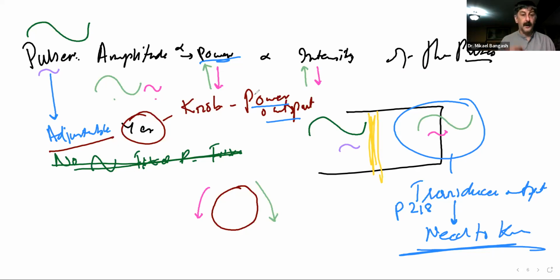Now, acoustic, I told you, acoustical is just a fancy word for sound. Pulser power: greater pulser power, well, greater power produced by the pulser. Lesser pulser power, or power produced by the pulser, we may call it greater or lesser amplitudes of your sound waves. So that's why they say to begin with that your pulser also determines the amplitude. The amplitude of what? The sound wave that is going to be produced by the transducer.